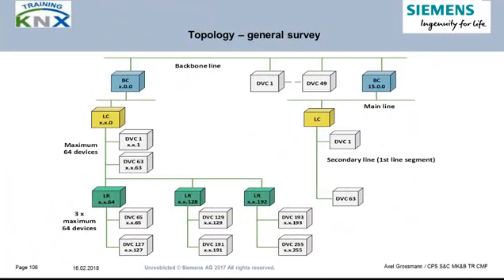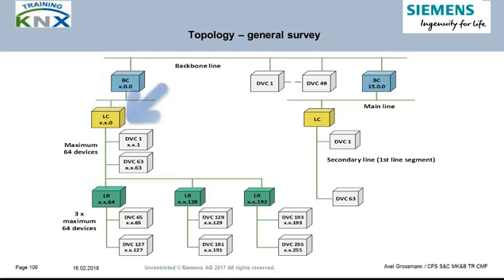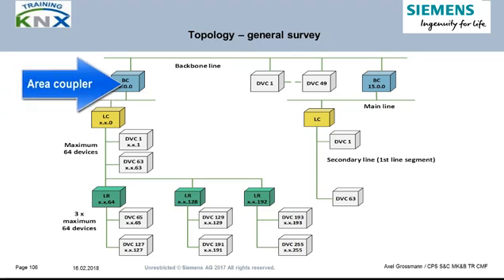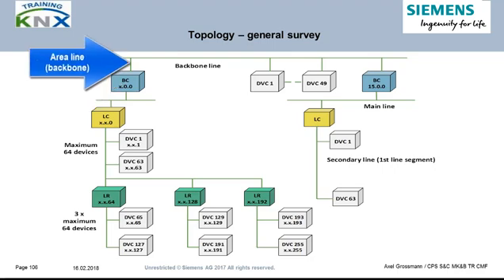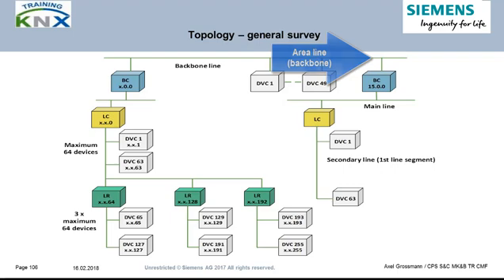This graphic shows a minimalistic general overview of the pure twisted pair structure, including all possible hierarchy levels. Without specific requirements, you always start with line 1.1 in ETS and assign the bus devices to the first segment of this line. In each line, a line coupler can be inserted — here yellow marked — to link up this line via the next higher level to other equally designed lines. Also this level, the main line, has couplers to the next level above.